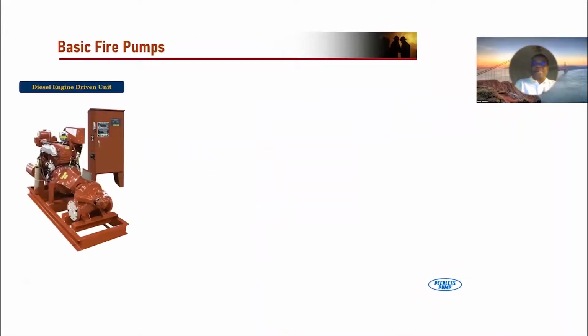Okay, let's talk about some basic fire pumps here. You can have a design of a fire pump, either from a contractor, and we can give you a simple diesel-driven unit, which would just be a diesel engine mounted on a skid with the pump, and then you can have the diesel controller and other accessories shipped loose. It will be something like this. It's very simple, so most of the assembly is actually done on site. The customer has to connect that to their own piping. They have to look at the NFPA 20 connection to make sure of the minimum spacing, the isolation valve, the check valves, and the relief valves, and things like these are all done at the job site. Okay, so that would be a diesel-driven unit.